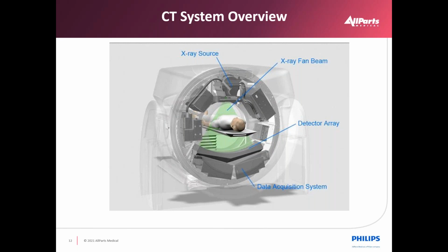And then we have a collimator, aka beam fan control. That's the output port of that X-ray tube. And represented here in that light green is the beam profile as it passes through the patient and hits the face of the detector. The detector converts X-ray photons that hit a crystal. The crystal then radiates visible light or infrared light, depending on the detector design. And that then is picked up by a photodiode. And the photodiode signal is then converted into a mathematical number. It's called A to D, analog to digital conversion, in a data acquisition system.